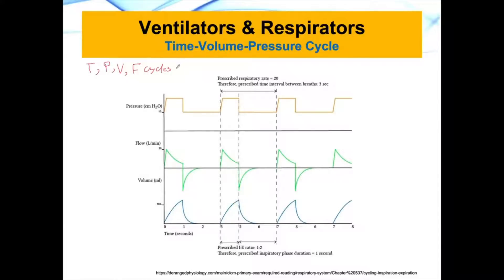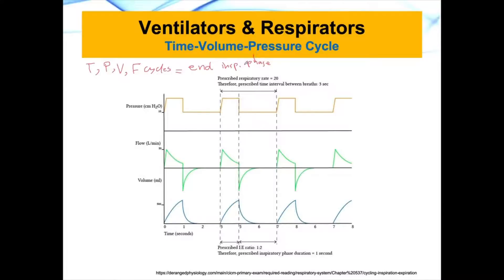Cycle — always keep in mind — it is ending the inspiratory phase. Keep that in mind, because that's very important. So when I say time cycle or pressure cycle, it's different from something called time control or pressure control. It's two different things.